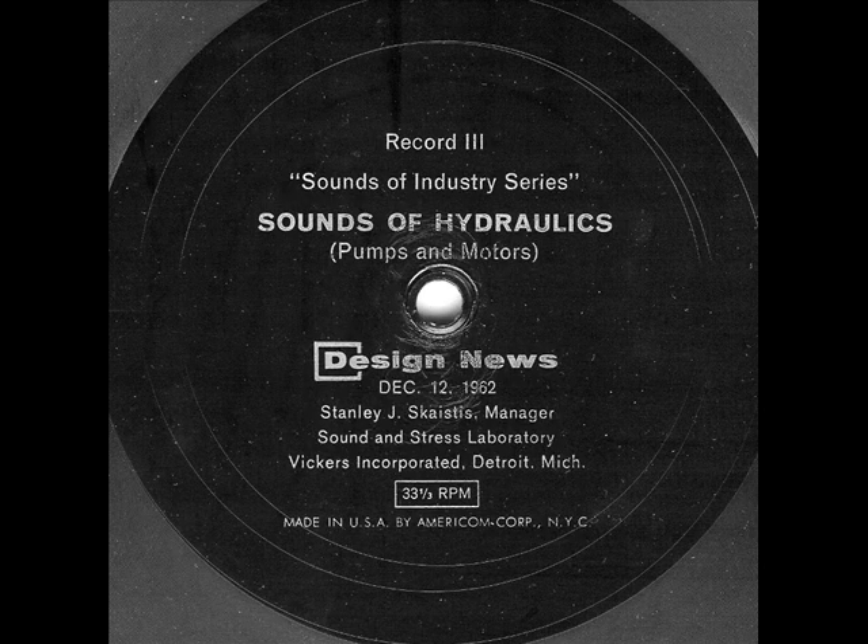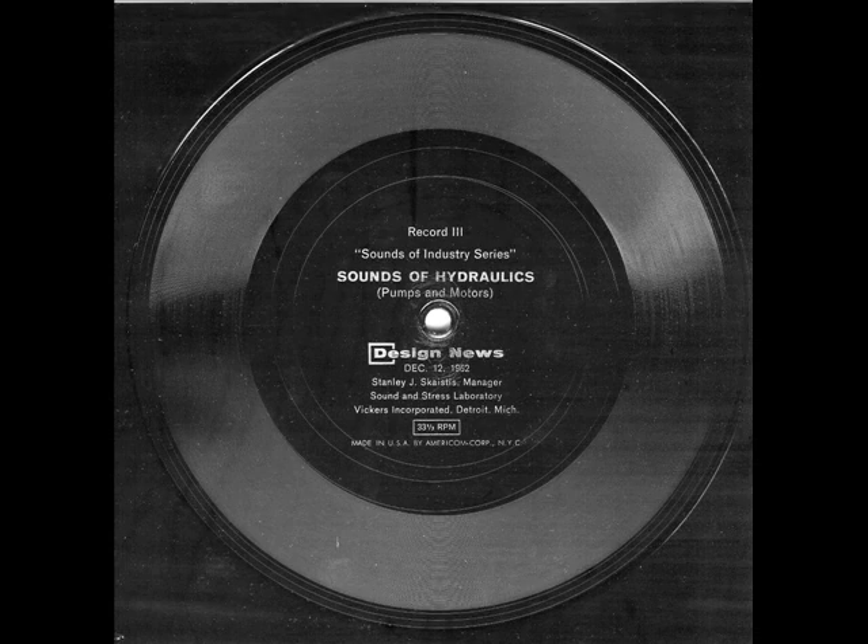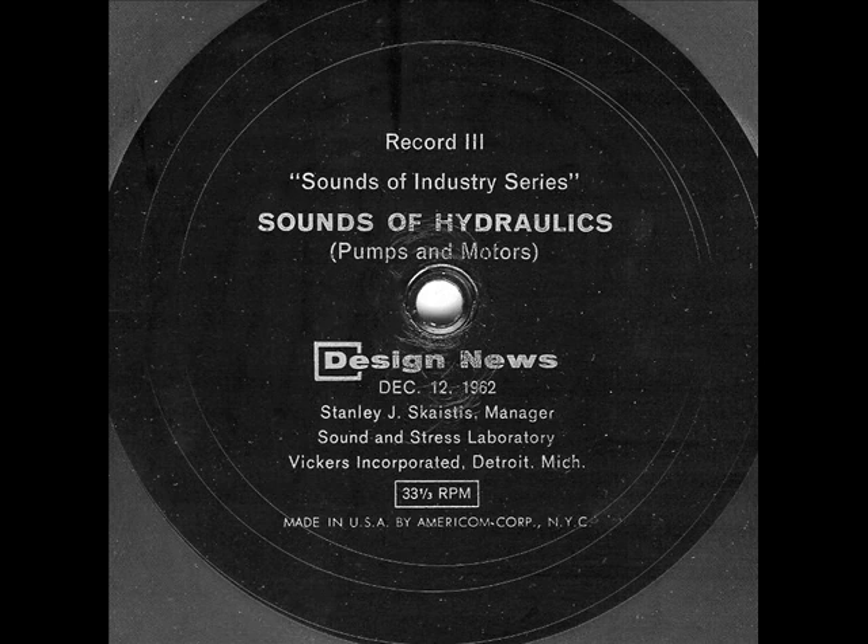This is the sound of a typical nine-cylinder pump operating at 1,800 RPM. The frequency characteristics of this sound are shown in figure two. Note the highest noise levels occur at multiples of the fundamental frequency, which is the frequency of pumping events — at the second harmonic, at the third harmonic, at the fourth, and at the sixth harmonic. This demonstrates that all major noise generated by a positive displacement pump will have a frequency which is some multiple of the fundamental frequency.